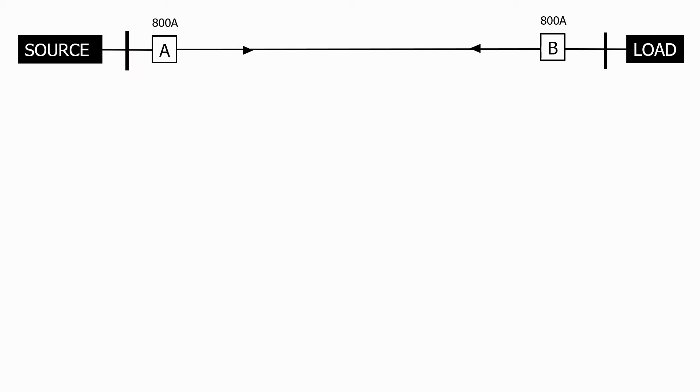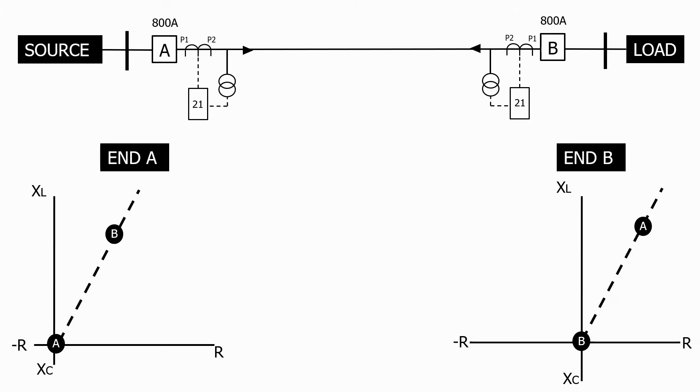We do this by putting an impedance relay at each end of the feeder. We set up a zone 1 for end A and a zone 1 for end B.